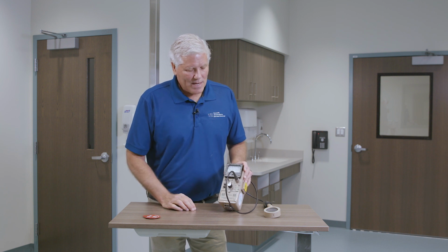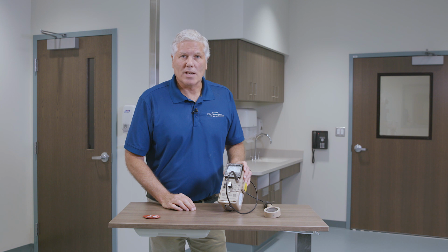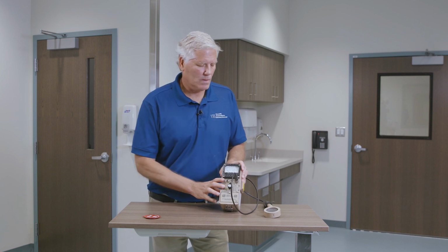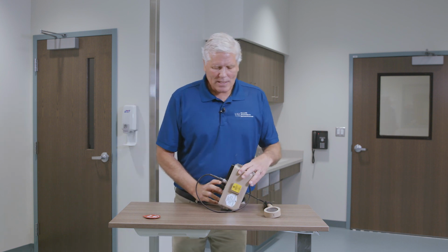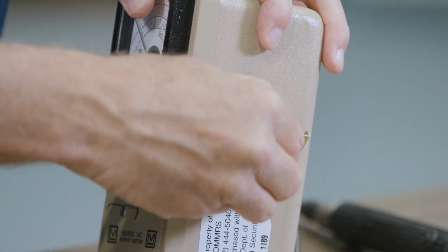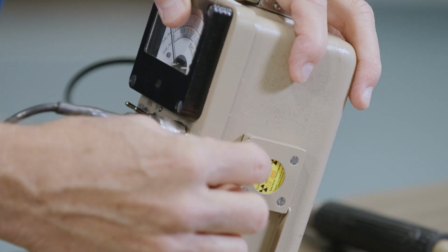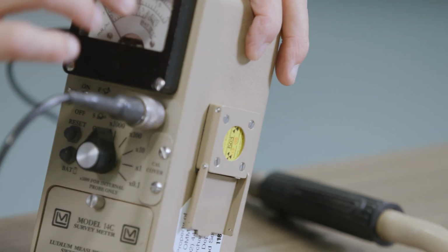After we've done that, our next thing we're going to do is a function check to make sure that the meter is responding accordingly. So once again, on most of these meters, you're going to have a check source adhered. Sometimes it's a thorium gas mantle. In this case, once again, it's a cesium-137 button source.